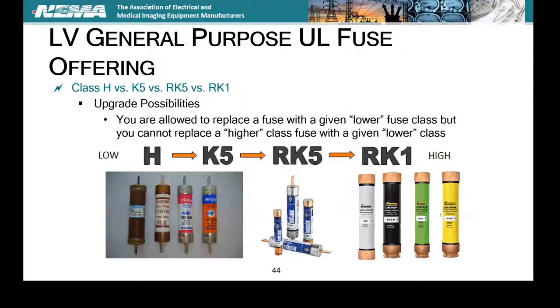So there's all of your different fuses right there, and there's your rejection features on the right down the bottom. You'll see that little nipple down there, a little nub that acts as a rejection feature, and that first general purpose gray fuse there doesn't have any of that. So that's a non-current limiting device. Some of them will have indicators to tell you they were opened.